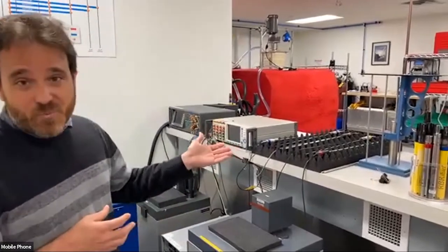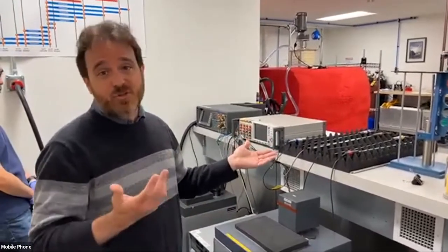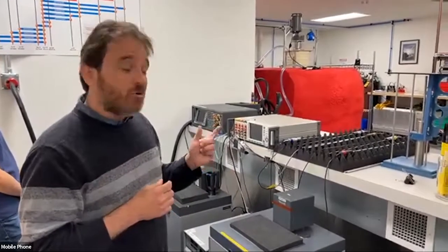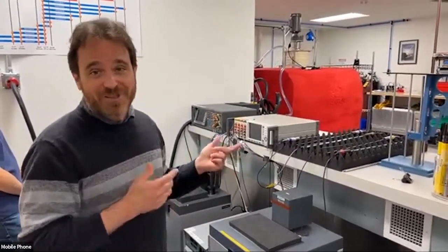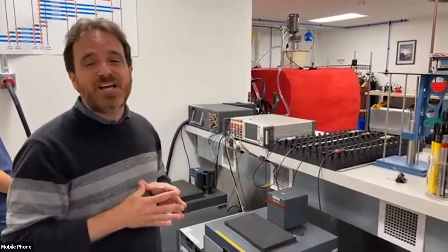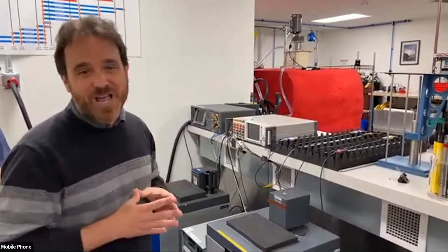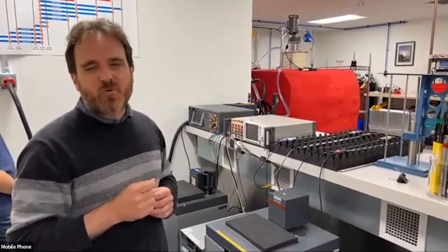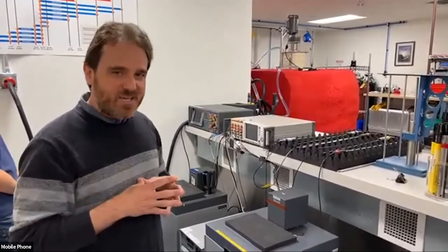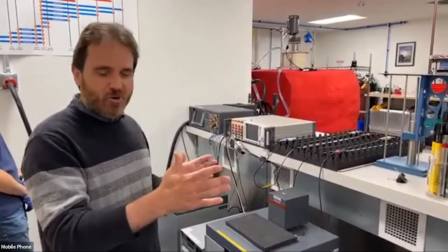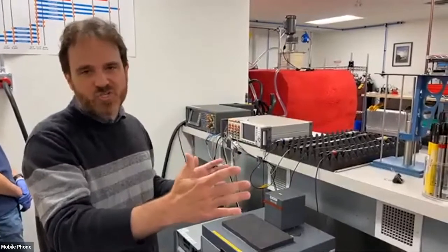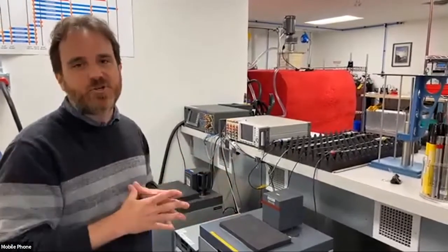I do want to mention that we do our own verifications and/or calibrations of our reference thermometers in-house in order to assure that we have reference instruments that are maintained within their accuracy tolerances. So the way we do this is we perform 2 primary realizations that are basically the endpoints of that range that I talked to you about, -5 to 35.